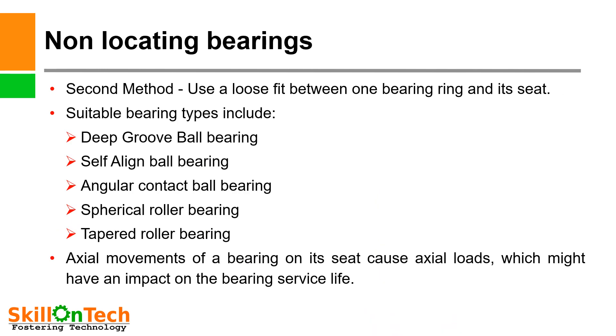Non-locating bearings — the second method: use a loose fit between one bearing ring and its seat. By keeping a loose fit, it provides space for axial displacement. Suitable bearing types include deep groove ball bearings, self-aligning ball bearings, angular contact ball bearings, spherical roller bearings, and tapered roller bearings. Note that axial movement of a bearing on its seat can cause axial loads which might impact bearing service life. If axial displacement clearance is not provided within the bearing, the axial load will impact the bearing and cause it to fail.